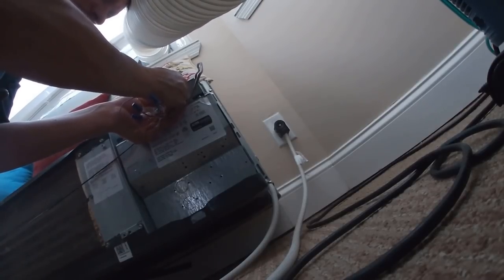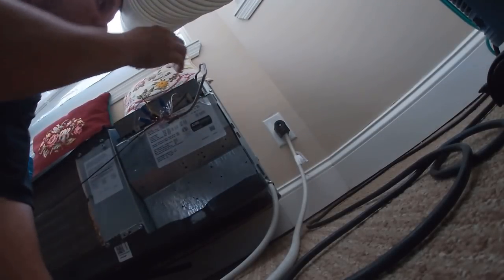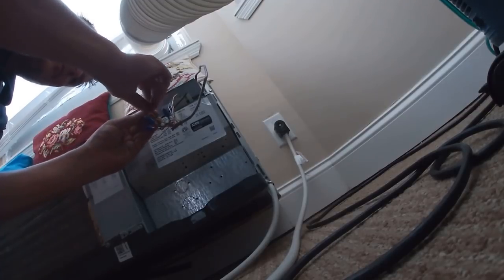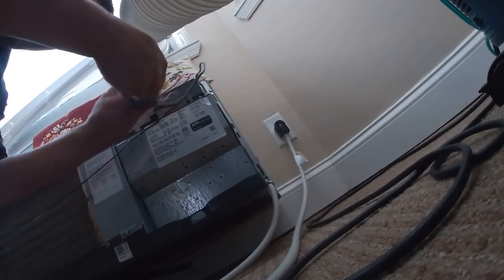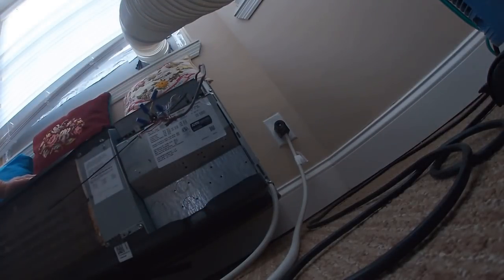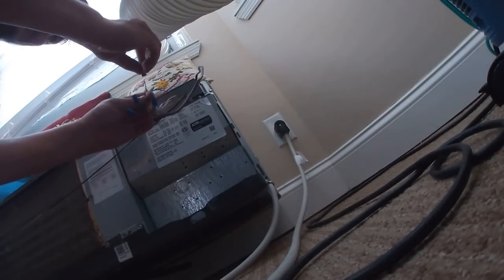Let me make sure I have this in the right slot. It timed out. Why did it go to yellow? You can't go by color here — yellow goes to reversing valve. But check this out, it just went into heat mode.